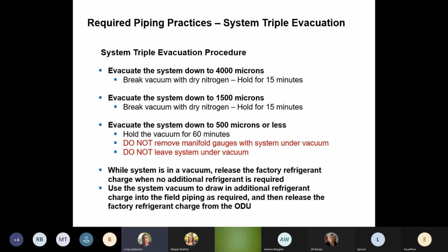If you don't add that when the unit is under a vacuum, then chances are when you crack the outdoor unit and throw the charge from the outdoor unit, there's not going to be enough gas in that unit to make your low pressure switch function. So now you're going to have to get into jumping low pressure switches and stuff like that to get it to turn on so you can add your gas to the unit. So always add your gas while the unit is in a vacuum. It's a little bit easier.